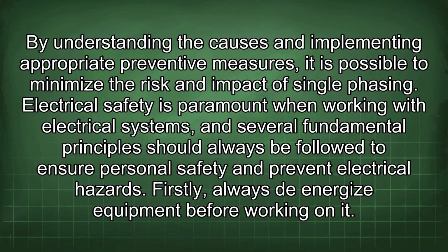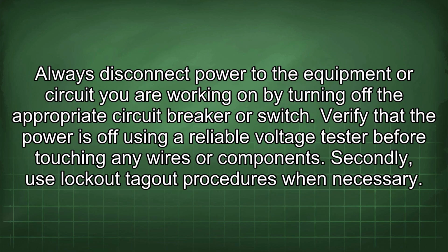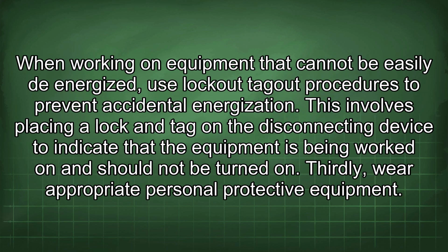Firstly, always de-energize equipment before working on it. Always disconnect power to the equipment or circuit you are working on by turning off the appropriate circuit breaker or switch. Verify that the power is off using a reliable voltage tester before touching any wires or components. Secondly, use lockout-tagout procedures when necessary. When working on equipment that cannot be easily de-energized, use lockout-tagout procedures to prevent accidental energization. This involves placing a lock and tag on the disconnecting device to indicate that the equipment is being worked on and should not be turned on.